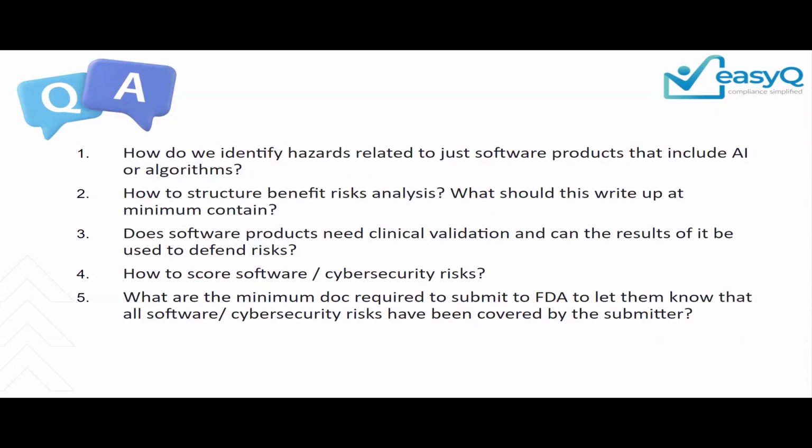You need to validate your software. Now the question is, how do you validate your software? Do you do clinical studies? Do you do simulated studies? Do you use databases? It's completely up to you. Based on the product that you have, you can take the route of clinical validation, or you can take the route of existing databases that are available nowadays for ECGs. There are so many internationally acclaimed databases that you can use to talk about the performance of your ECG algorithms. And these are actually biological databases.